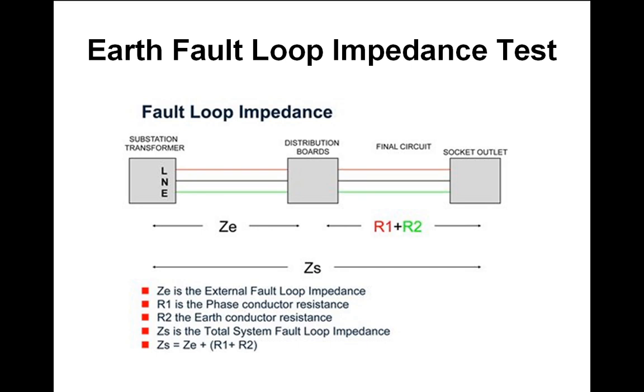What's going to happen? What is the current going through the earth wire, and is it going to be enough to trigger the fuse, to let the overload kick in? That's really what we are trying to find out and what we need to calculate.